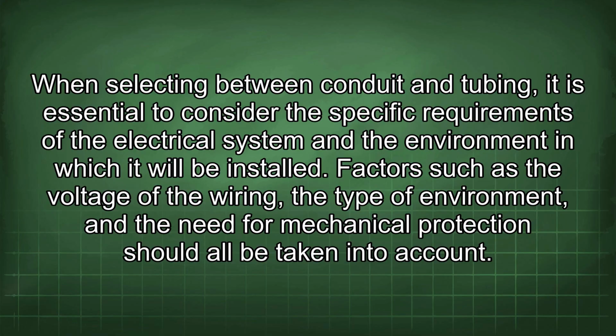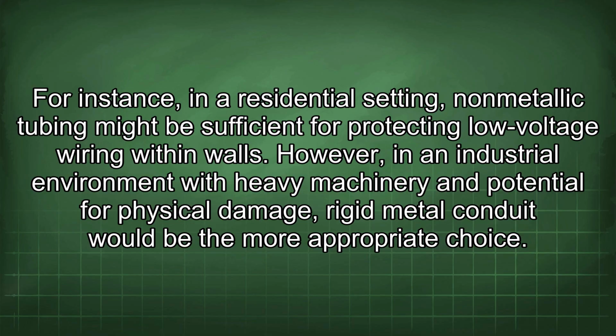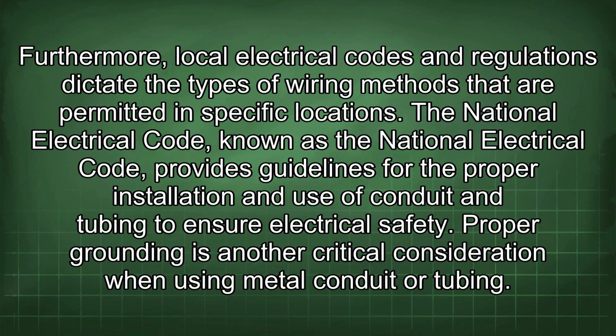Factors such as the voltage of the wiring, the type of environment, and the need for mechanical protection should all be taken into account. For instance, in a residential setting, non-metallic tubing might be sufficient for protecting low-voltage wiring within walls. However, in an industrial environment with heavy machinery and potential for physical damage, rigid metal conduit would be the more appropriate choice. Furthermore, local electrical codes and regulations dictate the types of wiring methods that are permitted in specific locations. The National Electrical Code provides guidelines for the proper installation and use of conduit and tubing to ensure electrical safety.